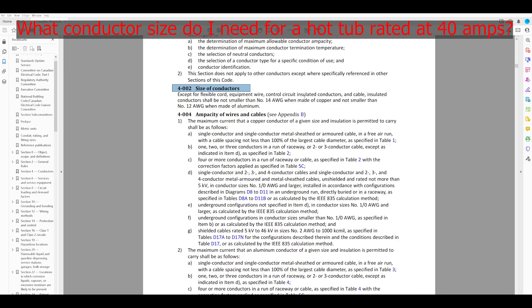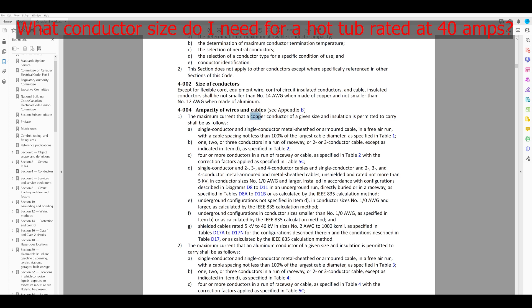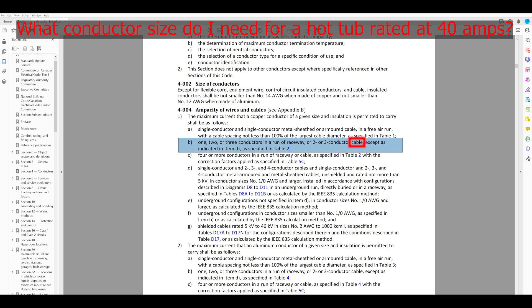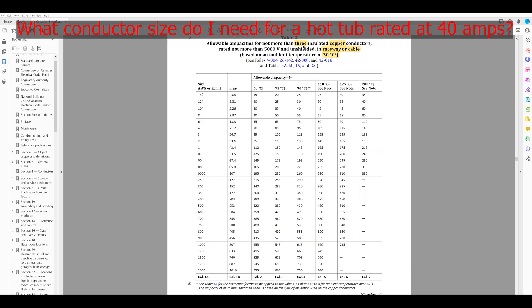Size of conductors — close. I don't see anything about hot tubs specifically. Ampacity of wires and cables: when we talk about size, size essentially refers to the ampacity value, because the size is based on how many amps that conductor can carry. The maximum current that a copper conductor of a given size and insulation is permitted to carry shall be as follows. So we've got free air — that's not us. Table 2 is going to tell us a given size based on ampacity.